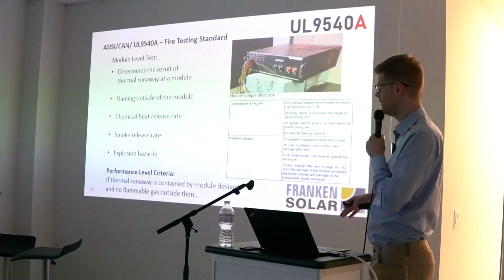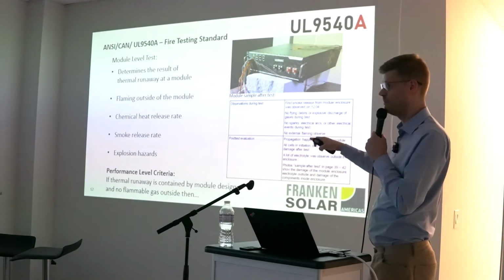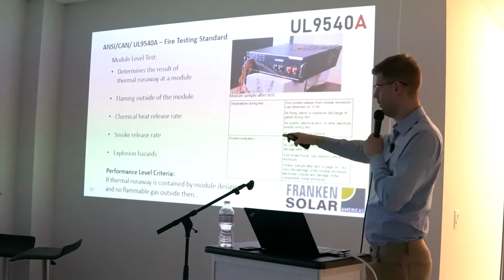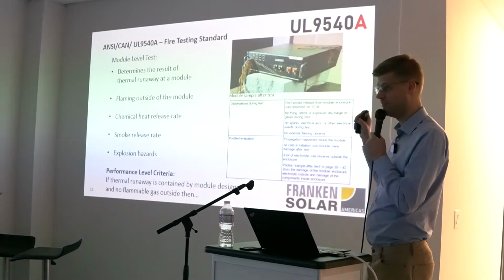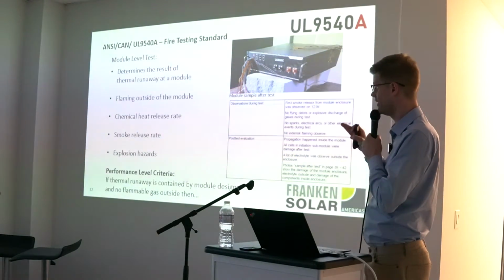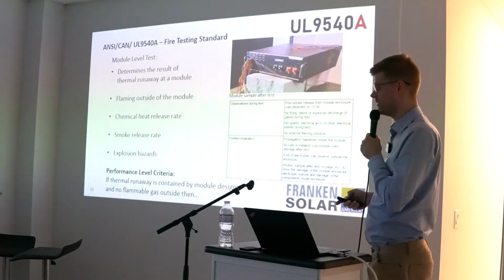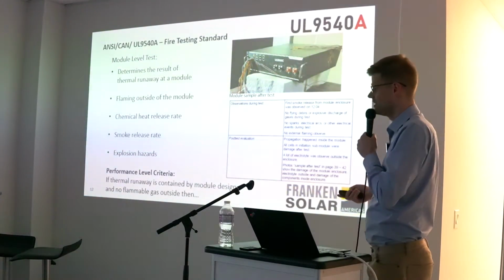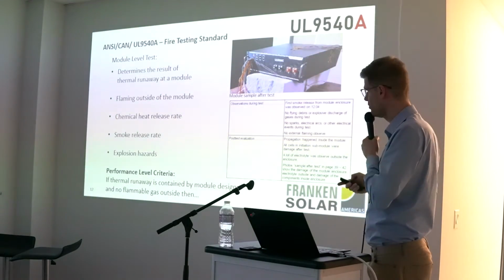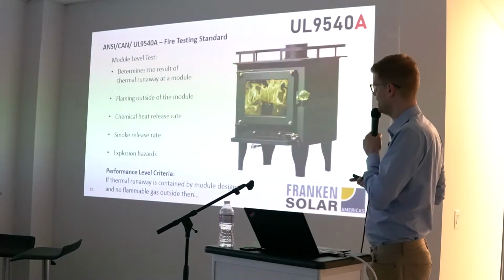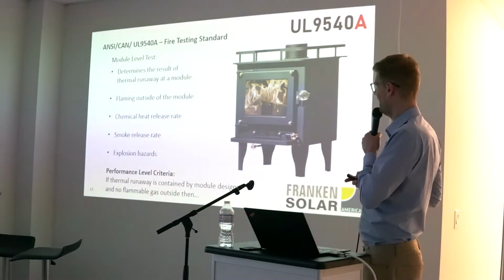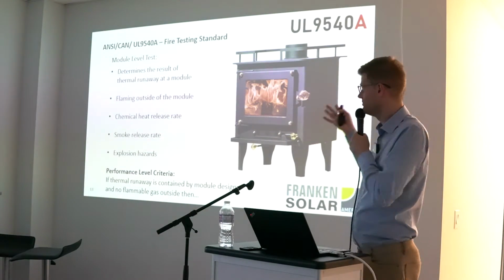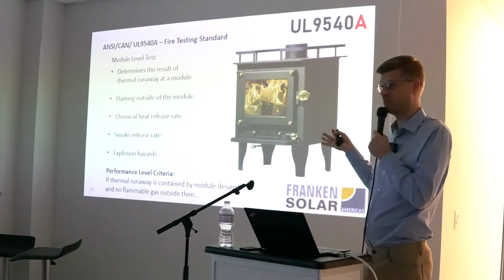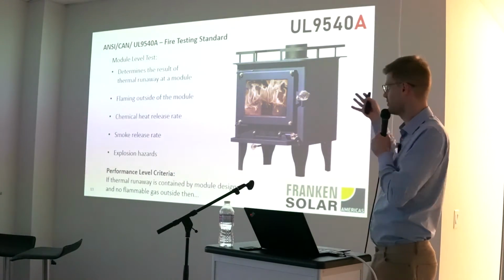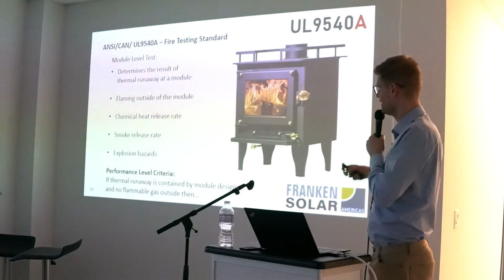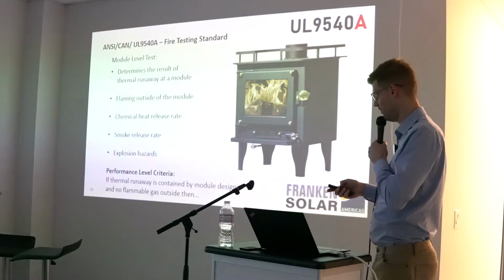Quickly, the performance level criteria. If the thermal runaway is contained by the module, which in this test we've seen it is, and no flammable gas is coming out, then that criteria is confirmed and you can stop the test at this point. If that's not the case, because you have a different chemistry, or the layout of the module is not up to par, or there are some issues with the design... or wait a second, that's my analogy. If that is tested, then you have like a wood stove in your house. So yes, there is fire in the wood stove. You have controlled the fire in the stove, and the stove itself is still safe because everything is designed to handle that fire or smoke within your house.